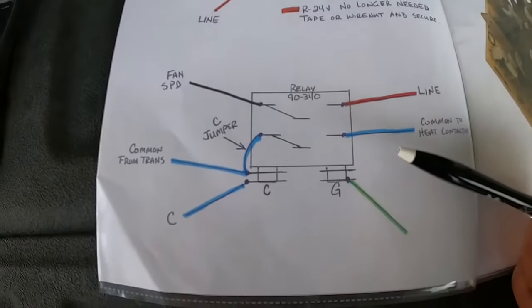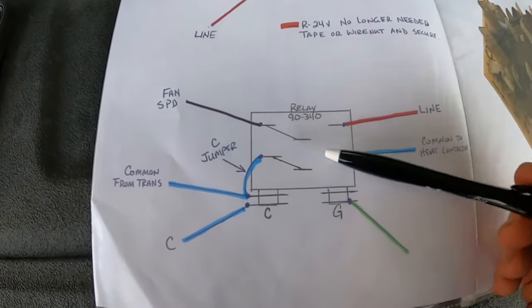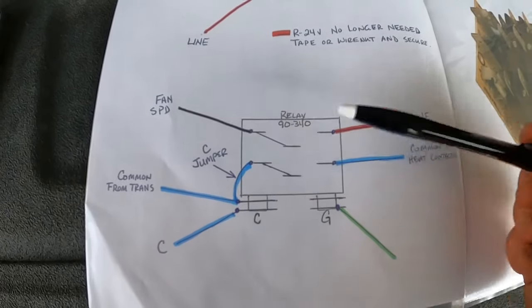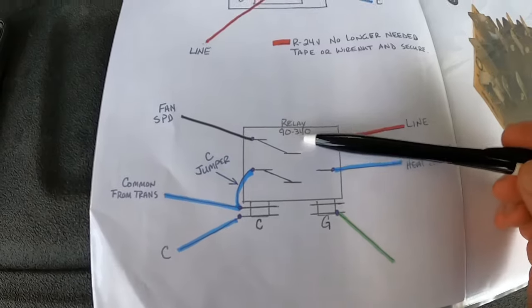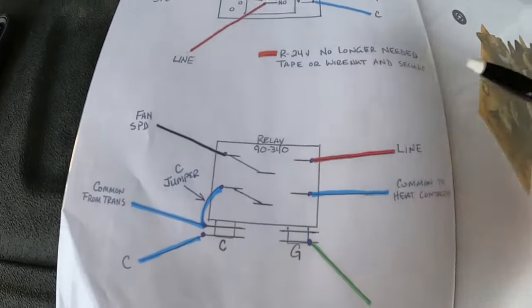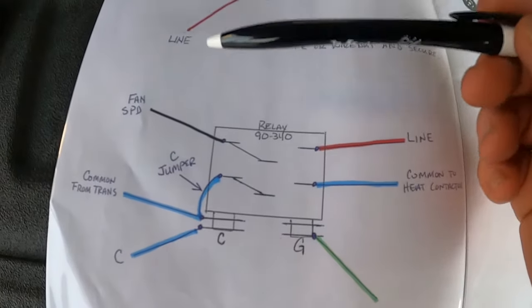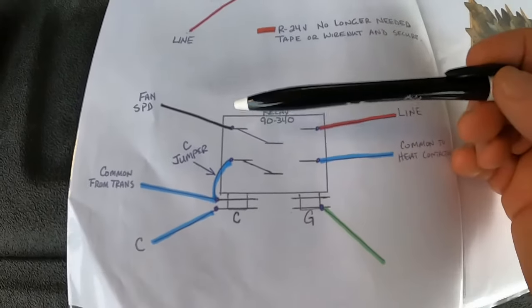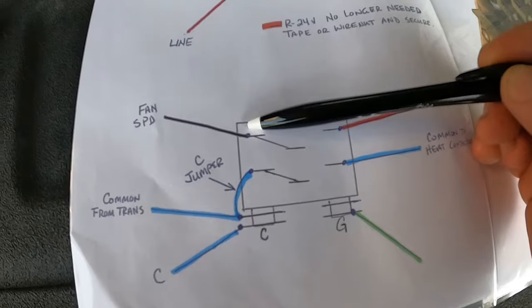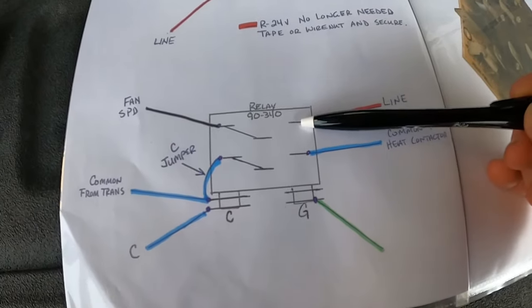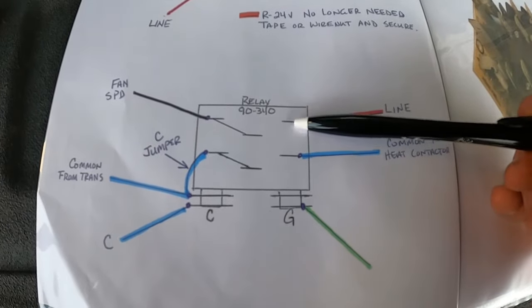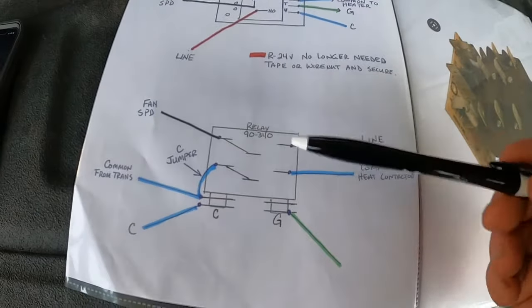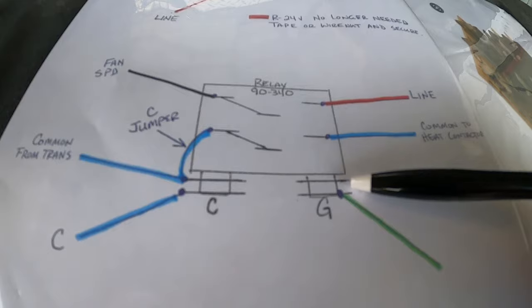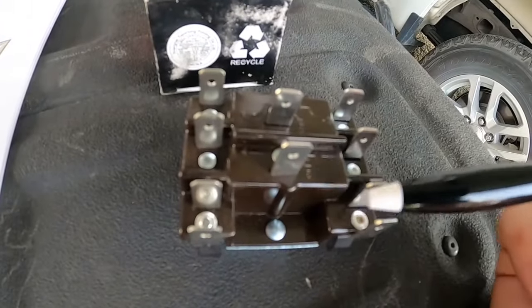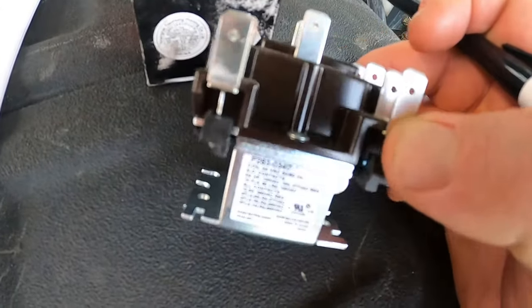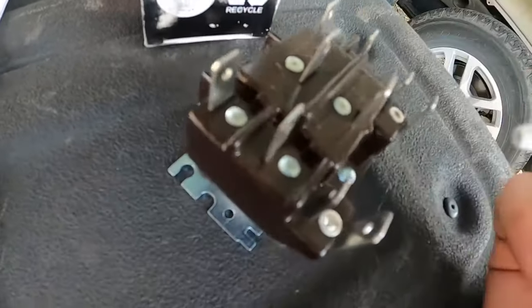Closes, blower comes on. With this relay, it's a double pole, double throw relay. So you have a switch here, and you have a switch across here. You got a normally closed, normally closed, normally open, normally open. With all these scenarios, in any scenario, your fan speed off your blower is always going to be your common terminal. So if you always remember to put your common fan speed terminal right there, your line voltage in to power that blower when this thing closes on the top right corner, you've won half the battle there, because you already know your low voltage is going to go here and here, which is going to be these 2 sets of terminals here that go to your low voltage coil on that relay. Right there and right there.